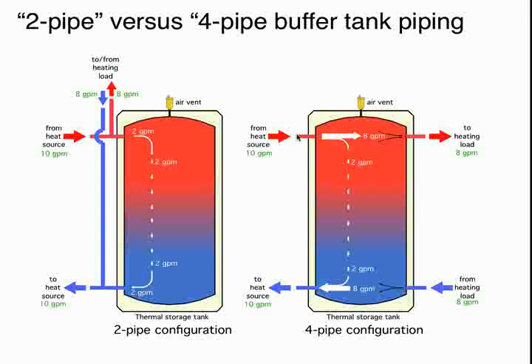Now, if we had the same scenario as far as flow rates, but we used a 4-pipe configuration over here on the right, you can see that it would be 10 gallons per minute going in the tank. 8 would pass through the upper portion of the tank and go off to the load. We'd have the same 2 GPM going downward through the tank, and then the flow rates would recombine at the bottom. The difference here is right up here at the top. We're getting more flow into the tank. That implies higher local flow velocities inside the tank. Anytime we have higher velocities in a tank, we tend to get currents in a tank that will tend to stir the tank. And one of the important concepts that we're going to look at in a few minutes, we don't want to do that.